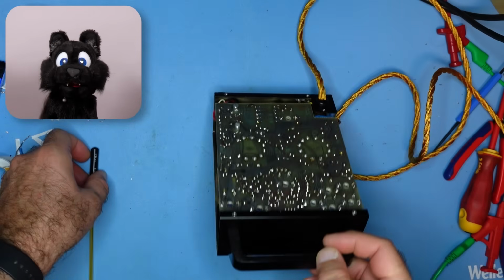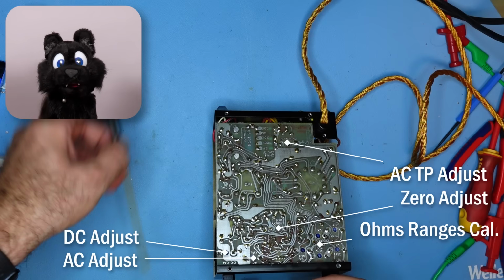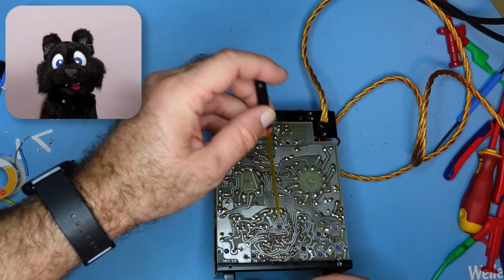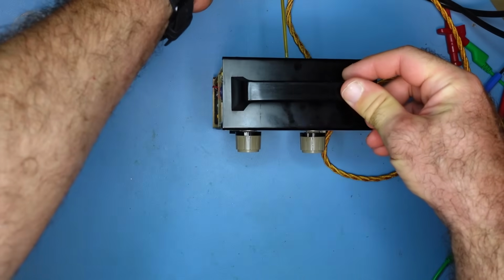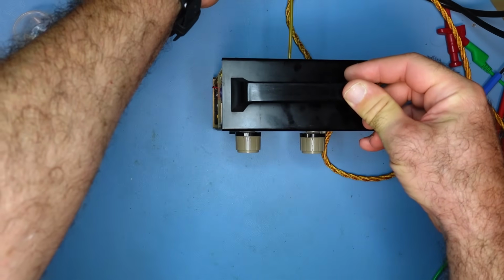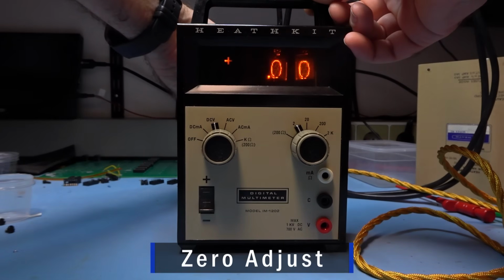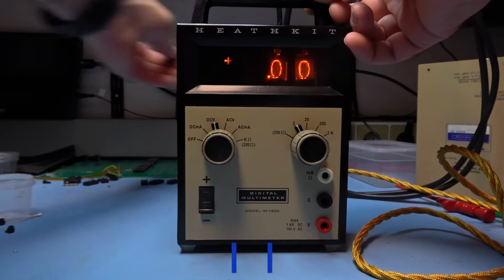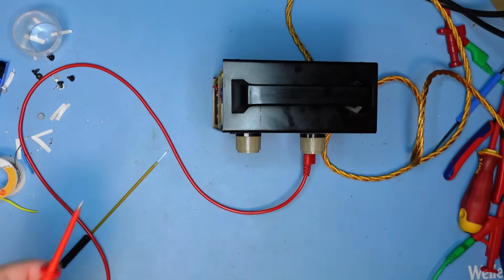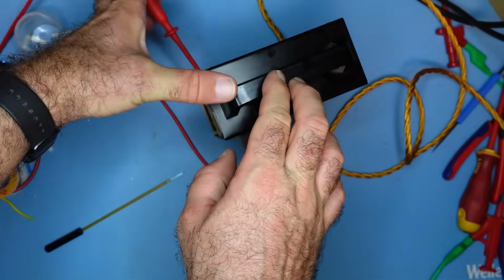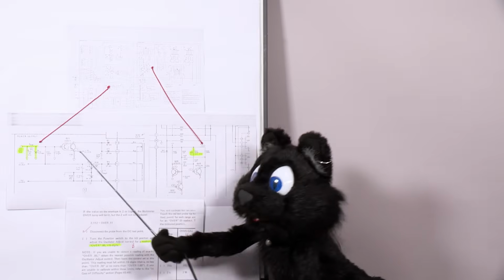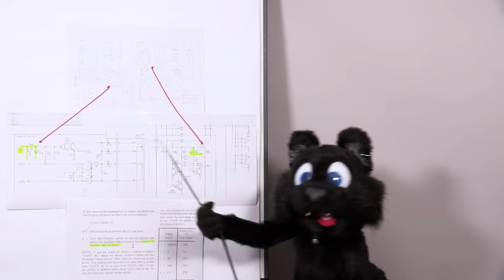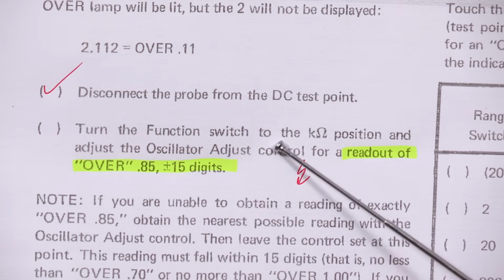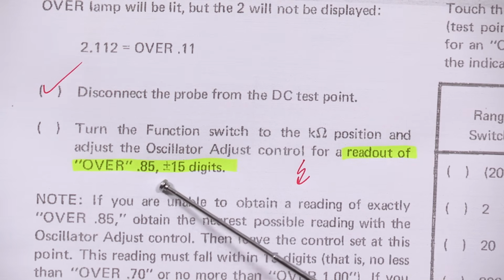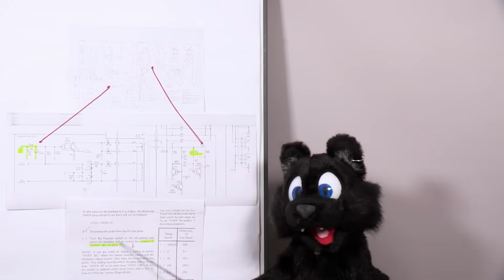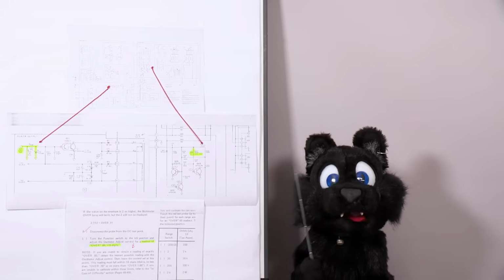Now to the calibration. The meter has calibration test points on the rear and quite a few trimmers for ranges. I tried to follow the calibration guide but ran into a few problems. After calibrating the DC voltage to read the correct voltage from the DC test point, it says to switch into Ohms mode and tune the oscillator so that the display reads overflow and 0.85 with a tolerance of plus minus 15 counts. So anywhere between 0.7 and 1.0 would be okay.